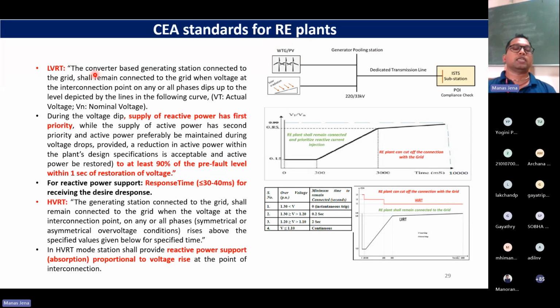So the converter based generation stations connected to the grid shall remain connected when the voltage at the interconnection point, POI, dips. I will encourage all of you to go through the IEEE 2800 standard, because many times I have seen people get confused with POI, POC, PON. This should not happen. We should be very clear about the abbreviations and where the compliance needs to be checked.